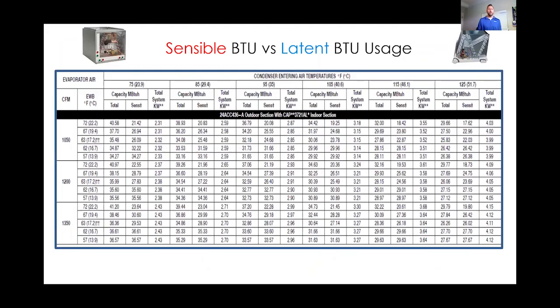All right, I don't want to get over technical on this one for you, but I do want to show you, maybe you're kind of like, Chris, yeah, you know what, our air conditioners do a fairly good job. And I'm not saying they don't, but here is a breakdown of a major equipment manufacturer's service manual. We have what's called sensible BTUs and latent BTUs. So you have total BTUs of that air conditioner. So if I was to reference a 3-ton system, that's 36,000 BTUs. A part of that is going to be sensible, which is our temperature change, which is cooling. And there's going to be a percentage that's latent, which is moisture change or moisture removal.